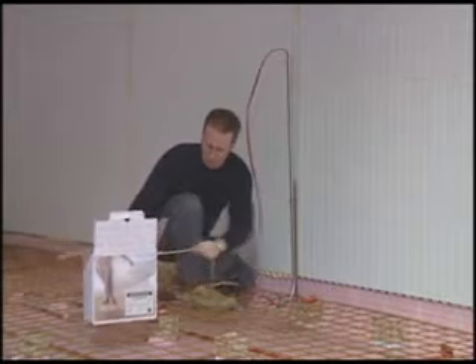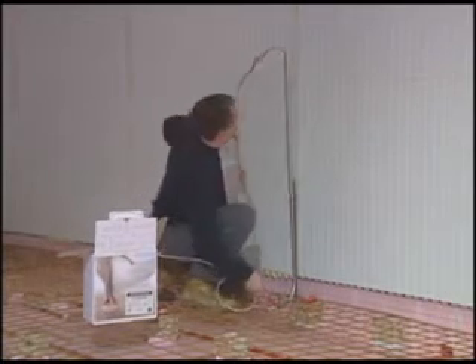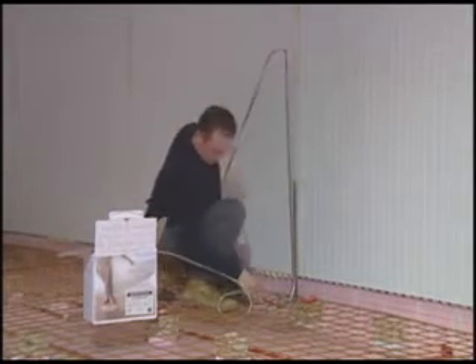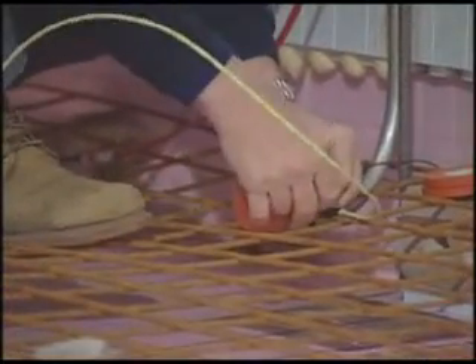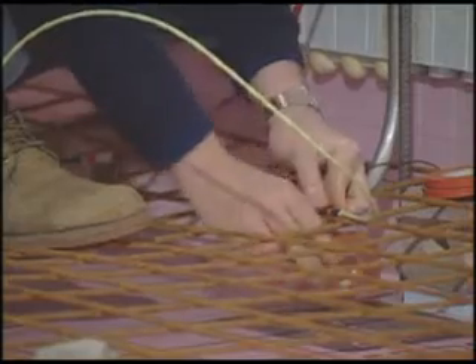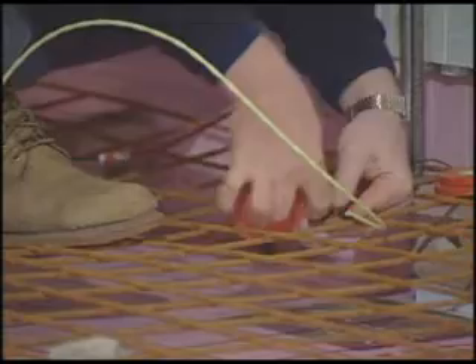Pull on the cable until the mechanical joint is about 12 inches from the conduit's lower end. Use Flextherm adhesive tape to attach the mechanical joint to the mesh. Ensure that the mechanical joint is attached outside the conduit and in the area where concrete will be poured.